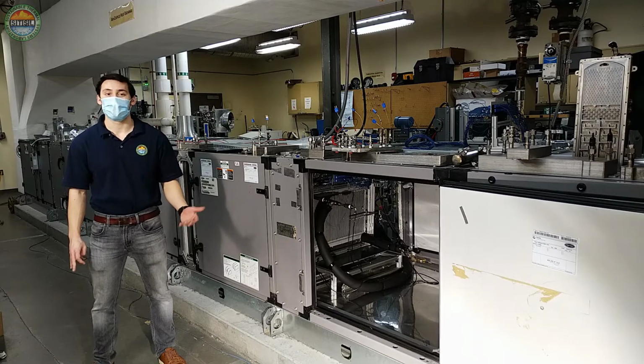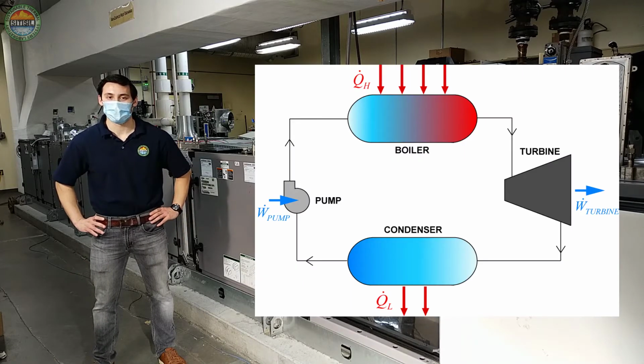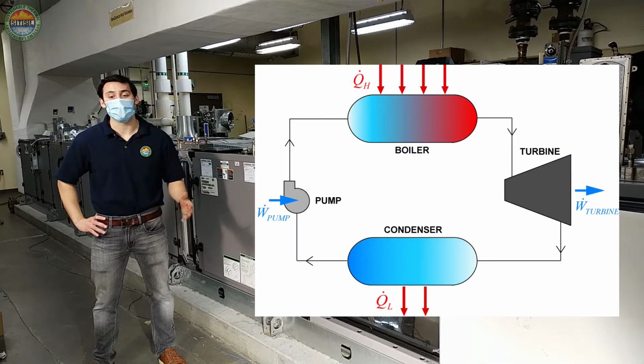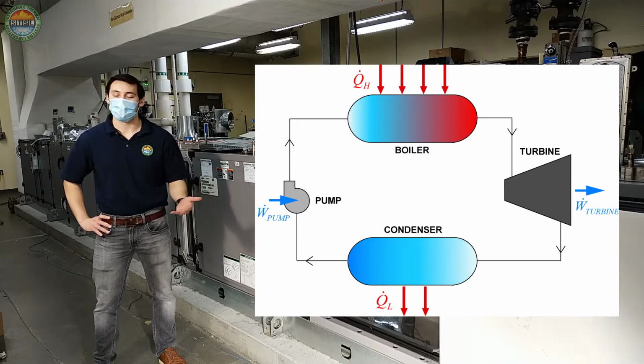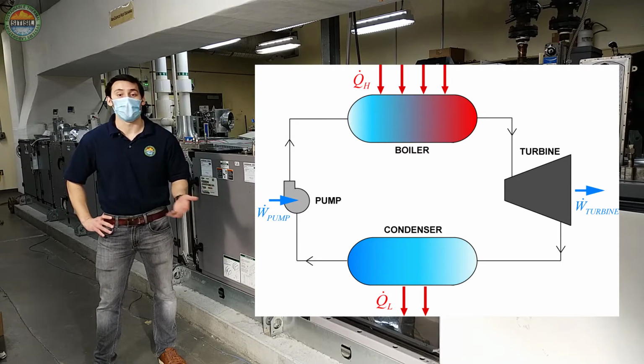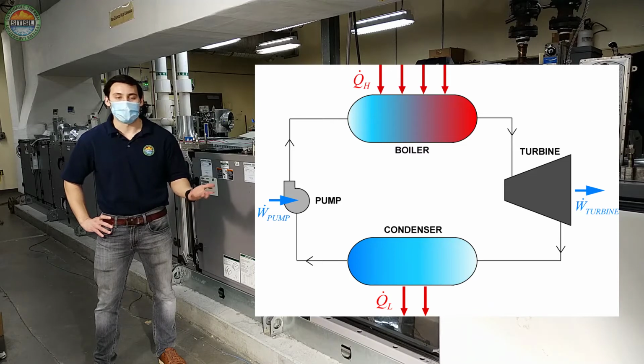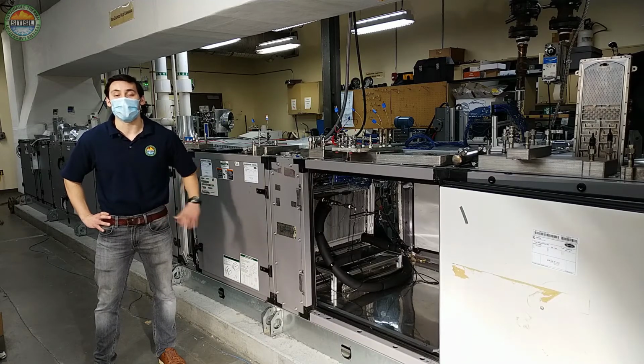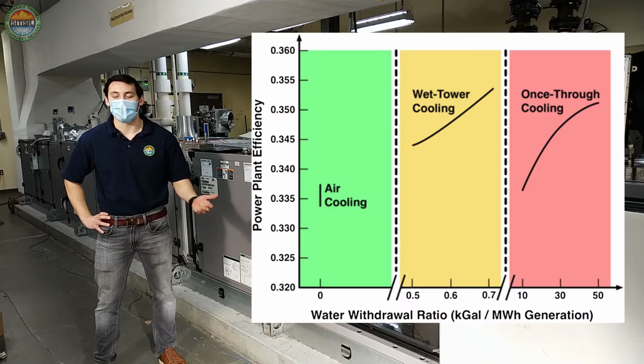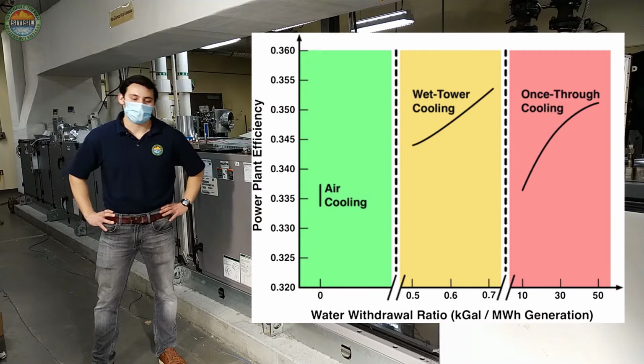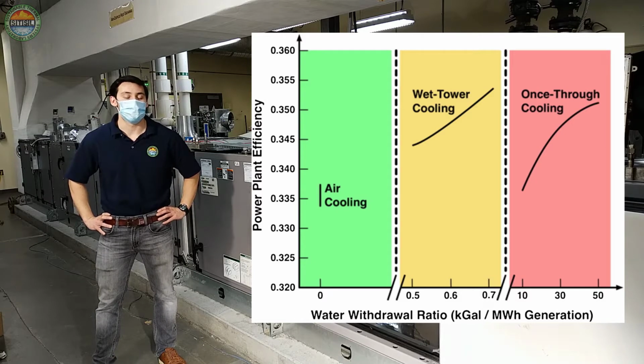Thermal power plants operate in what's known as the Rankine cycle. In order to condense the process steam leaving the turbine, we typically use a once-through water-cooled condenser or a water cooling tower. While these water cooling methods offer high power plant efficiencies, they also require large quantities of water. Statistically in the United States, power plants account for about 38% of freshwater withdrawals.